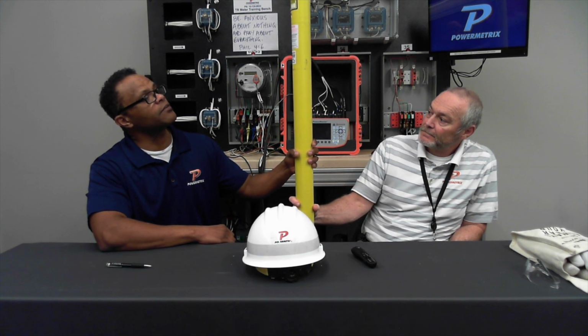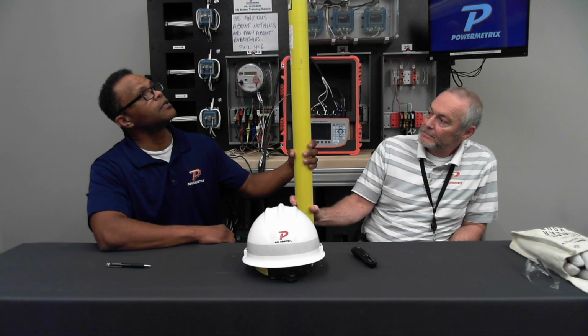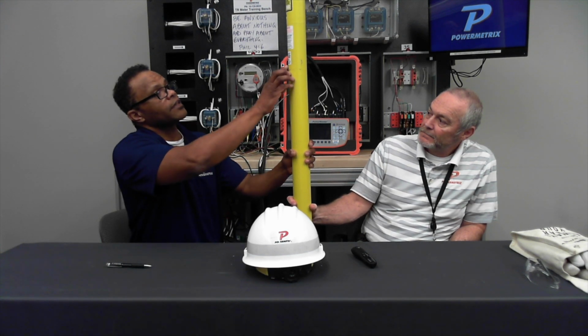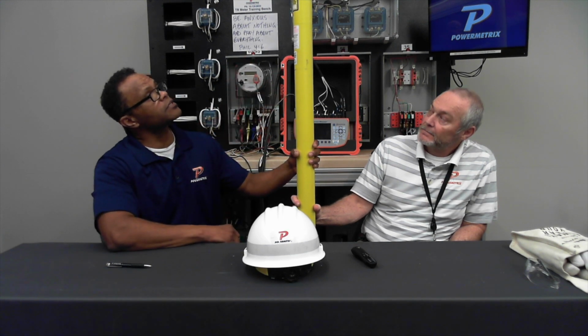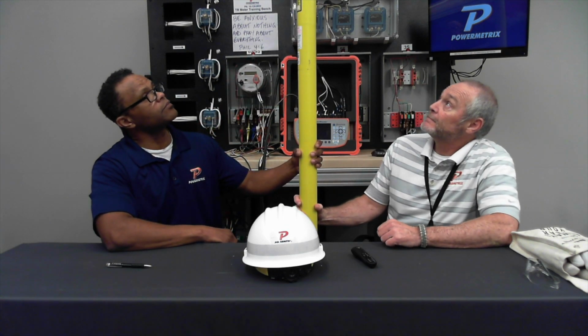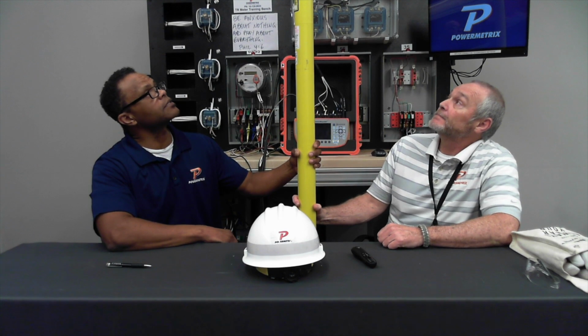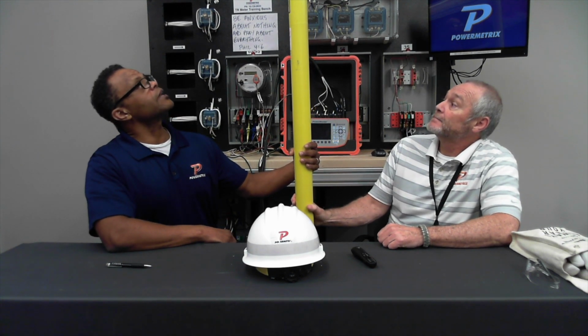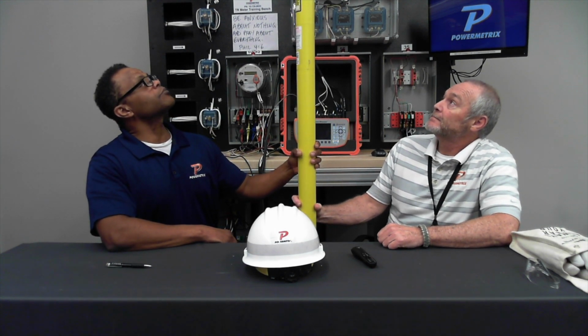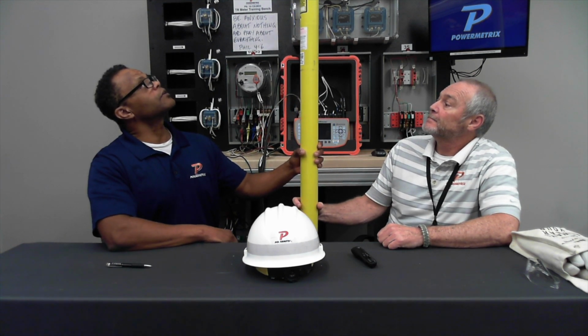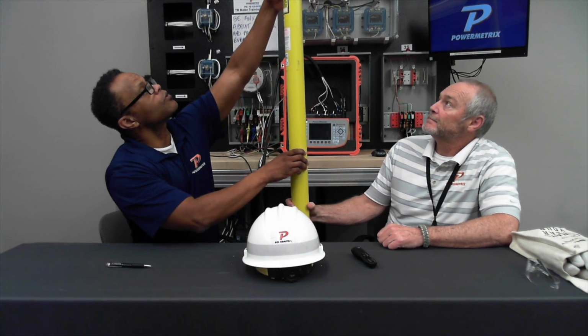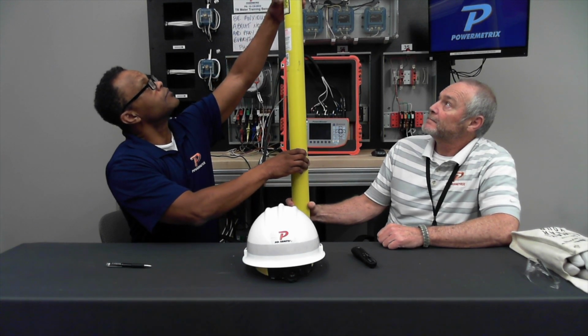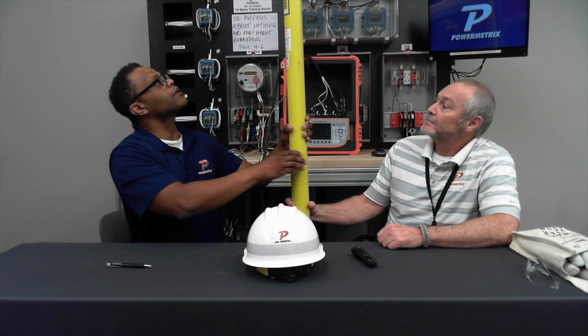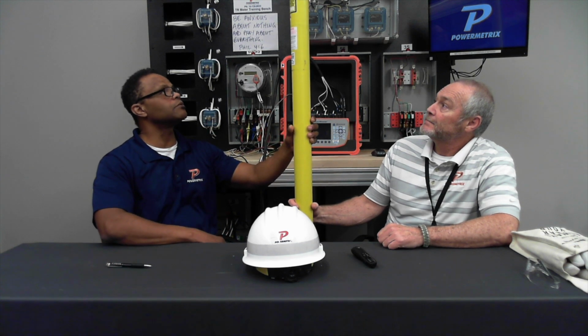And then it's actually giving me what they tested it as per foot. So they've got here 75 kV per foot. So what they did was run 75 kV per foot through this stick, and I'm sure they extended it out during the testing. This stick also has a date when it was manufactured, and a model number. So if you ever need different sections for it, you can order using that model number and manufacture date. That's pretty cool.